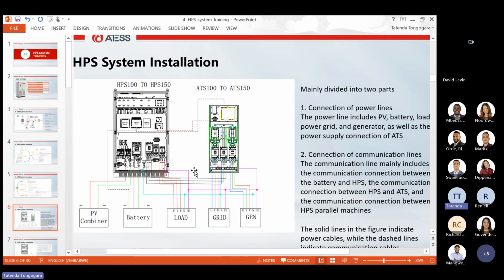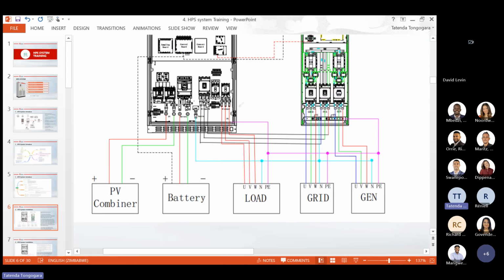So on the power side, I don't know if you can see. So we have the PV combiner, combine all your PV and then you connect it on the PV input. We have the battery input and then the load. As I said, we only have one AC input. So our AC input, one port. So if you have generator and grid, you can make use of the ATS. So grid and generator into the ATS, the output of this ATS, you connect it to your AC input.